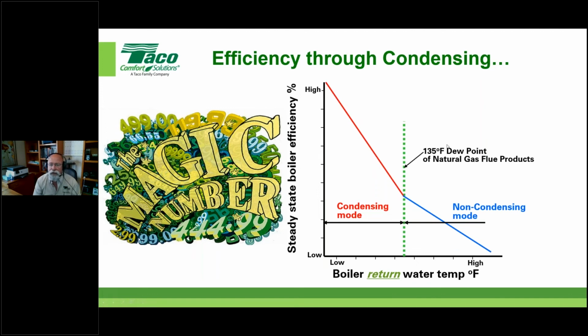It's low temperatures back. If you look at this chart that comes to us, I've seen this from ASHRAE, and almost every boiler manufacturer out there that sells condensing equipment uses something that looks just like this or similar to this to some extent. But you notice there's this magic spot in which the pitch of this curve changes quite a bit, right? And this spot here, it's pointing out that it's 135 degree dew point for natural gas flue products. But that's not the number we're looking for. That just tells you the science is happening back inside the combustion chamber and stuff. What we're looking for is a fluid temperature that's low enough so that the surface temperature can actually see condensation.